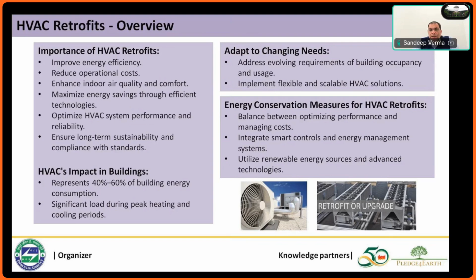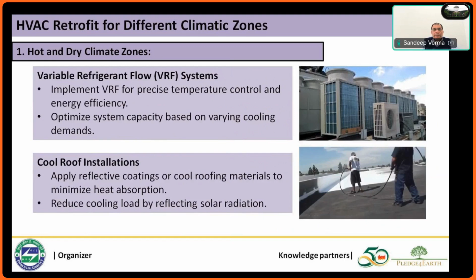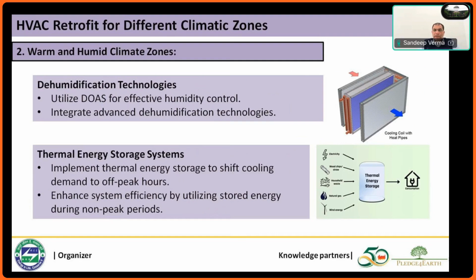For different climatic zones, we recommend different types of air conditioning systems. For a hot and dry climate zone, we can go for a variable refrigerant flow system along with a cool roof. For a warm humid climate zone, you can go for a dedicated outdoor air supply system, DOAS, along with humidity control. At the same time, you can go for a thermal energy storage system also, in order to utilize the variation in temperature during evening hours. So that can be done in the warm and humid climate zone.